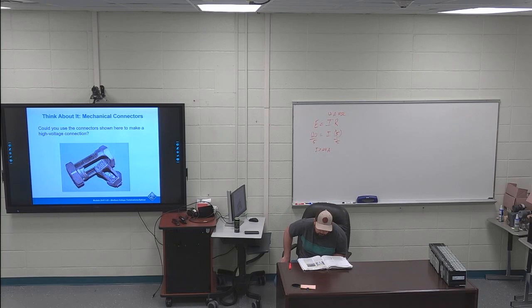No. The immediate next paragraph, skip a sentence and the rest of the paragraph is highlighted. Aluminum conductor should be connected with an aluminum body connector preloaded with contact aid, that antioxidant paste, to break down the insulating aluminum oxide coating on both the connector and the conductor surfaces. Aluminum corrodes or oxidizes, so you want to put that paste on there to make sure it doesn't oxidize. Oxidation can act as an insulator. You don't want an insulator in your splice where you don't want it.